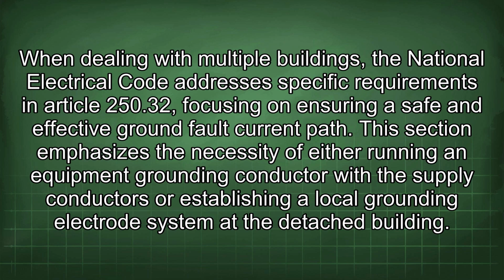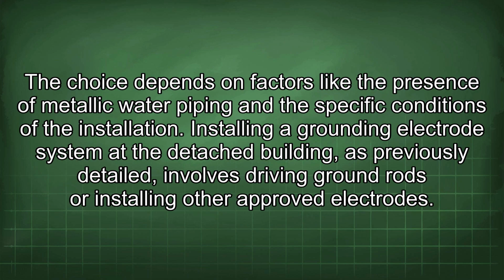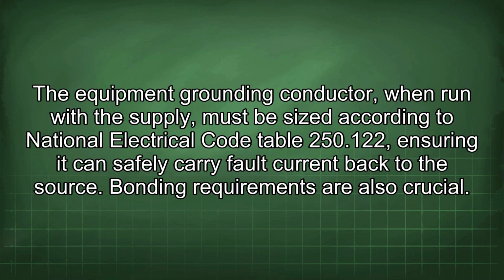This section emphasizes the necessity of either running an equipment grounding conductor with the supply conductors or establishing a local grounding electrode system at the detached building. The choice depends on factors like the presence of metallic water piping and the specific conditions of the installation. Installing a grounding electrode system at the detached building, as previously detailed, involves driving ground rods or installing other approved electrodes. The equipment grounding conductor, when run with the supply, must be sized according to National Electrical Code Table 250.122, ensuring it can safely carry fault current back to the source.